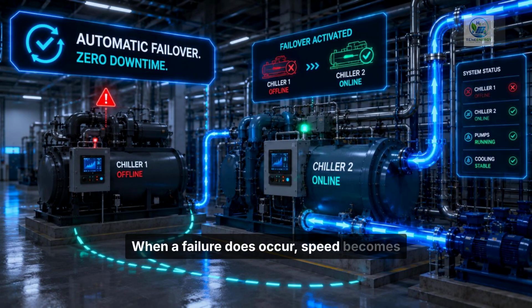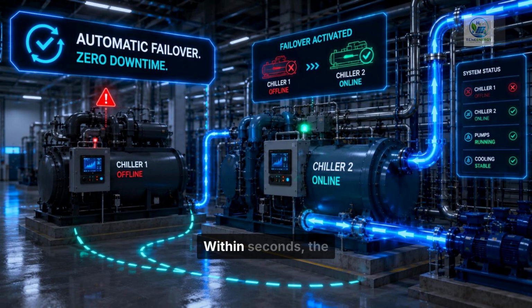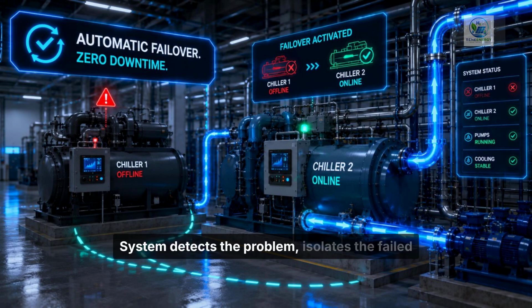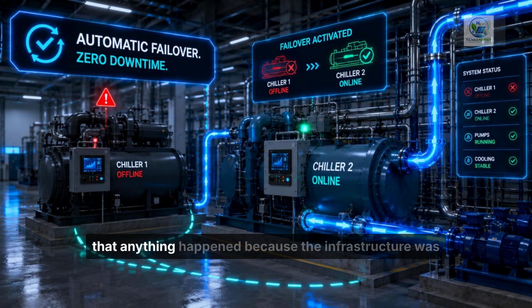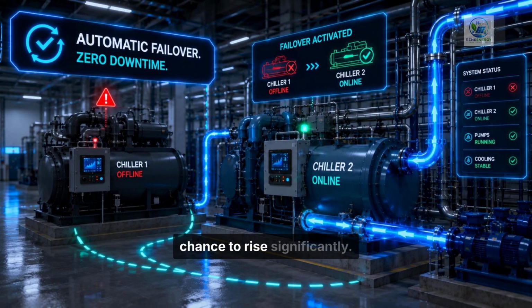When a failure does occur, speed becomes critical. Imagine one industrial chiller suddenly shutting down. Within seconds, the building management system detects the problem, isolates the failed equipment, starts a standby chiller, reroutes water flow through alternate piping, adjusts pump speeds, and restores cooling capacity, all automatically. This process, known as automatic failover, allows the cooling system to continue operating without interrupting the AI workloads running inside the data center. Most users around the world never notice that anything happened because the infrastructure was designed to recover before temperatures have a chance to rise significantly.